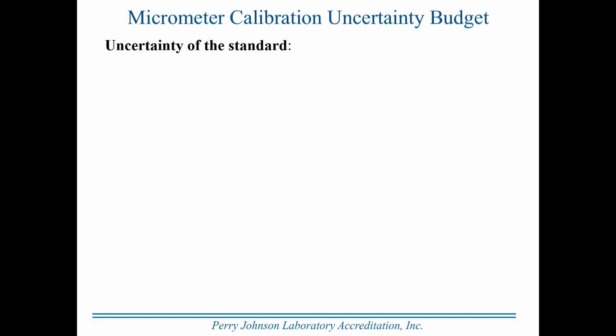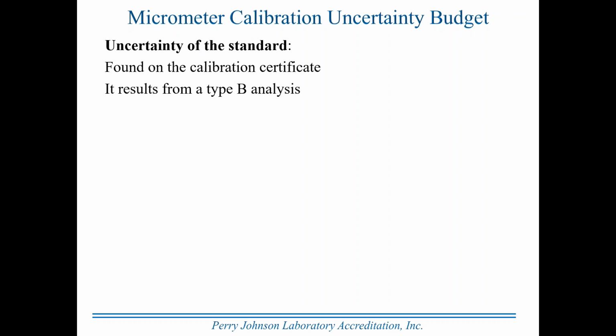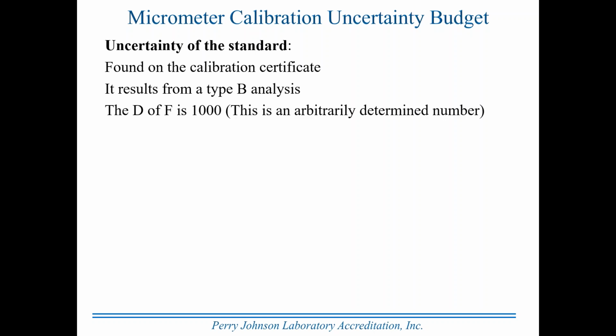All right, let's look at the uncertainty of the standard and how we're going to process it. It's found on the calibration certificate. It results from a type B analysis because we didn't do it statistically. Now, the laboratory that calibrated it may have done a type A analysis, because they did use statistics to arrive at it. But they give it to us as part of a document. It's printed information, therefore it's a type B analysis.